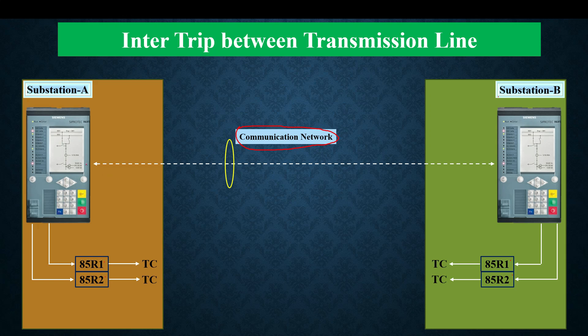The substation that sends the inter trip signal has already tripped its own circuit breaker. Simultaneously it sends the inter trip signal so the remote circuit breaker also trips. Inter trip is used for better protection of the network — if protection at one end operates but the protection at the other end fails for any reason, the inter trip ensures that the remote circuit breaker is also tripped, providing redundant protection for the transmission line.